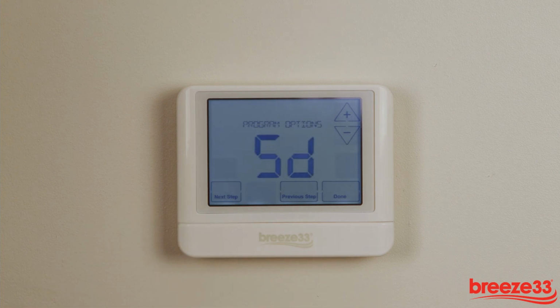Program options. You can configure this thermostat to have a 7-day program, a 5+1+1 program, or non-programmable. Use the negative or positive keys to select 7D for 7-day, 5D for 5+1+1, or 0D for non-programmable. The display light can be configured to operate in 3 different ways: to come on only when the light key is pressed, when any key is pressed, or stay on all of the time. The settings are auto, any key on, or on, always on.